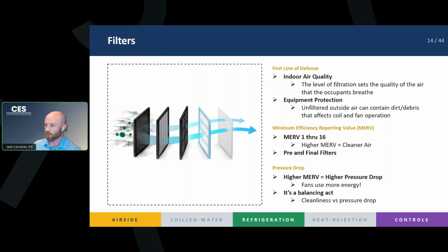You set them up in a pre and final filter often because, you can imagine that the higher the MERV, the cleaner the air, right? And so the more that you're going to capture on your filter, and maybe the more often you're going to have to replace it. So, if you can capture a lot of the big stuff with a low MERV filter, like a MERV 8, then you can have the MERV 13 downstream. You don't have to change out your high MERV filter, which could be much, much more expensive than your MERV 8. Maybe you change your MERV 13 twice a year, and you change your MERV 8s 4 times a year, so you don't have to continuously change your high MERV filters and spend a lot of money. That's just a common configuration, saves you money, and also gets you the high quality clean air you need inside.